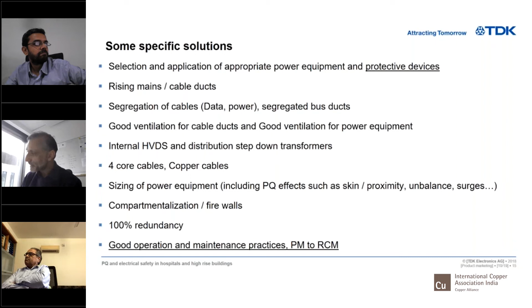This is not only at the building level, but even at the component level. If you're coming from the switchgear industry, whether you do low voltage or medium voltage switchgear, people today insist on certain forms. You have form 2B, 4B, compartmentalization and internal arc-proof panels. Today, I believe it's mandatory that we specify the panels with very clear compartmentalization and, depending on the requirement, internal arc-proof and the kind of construction.